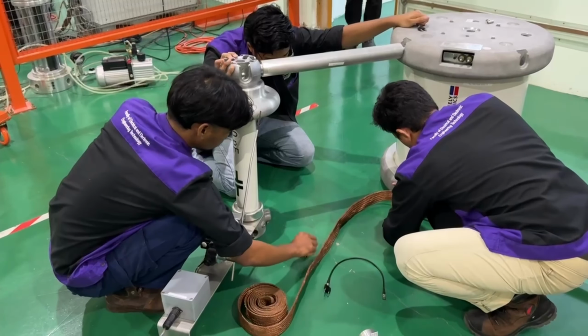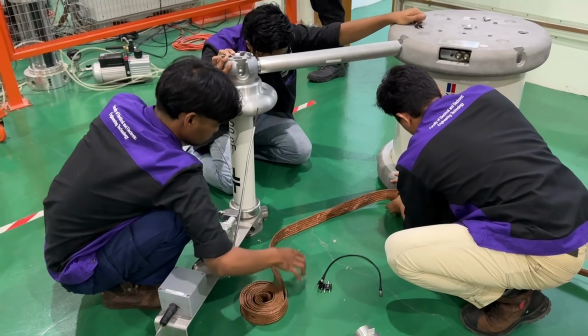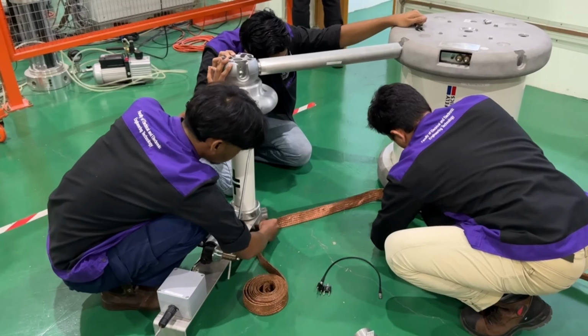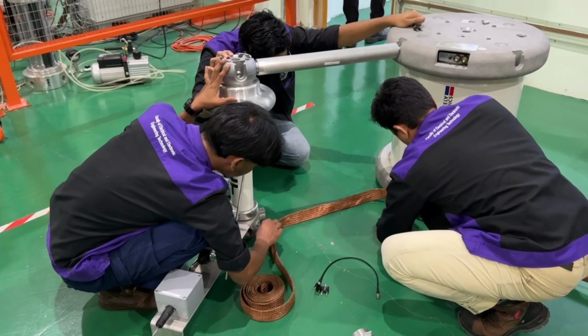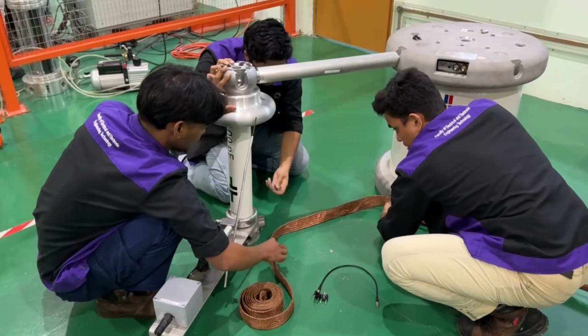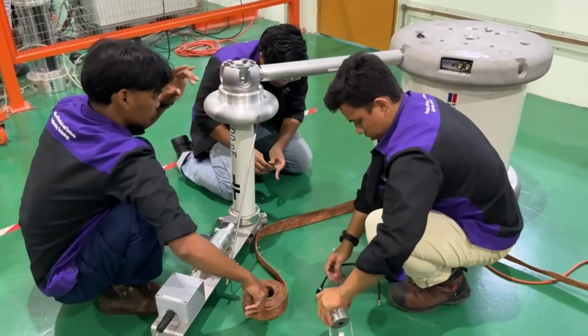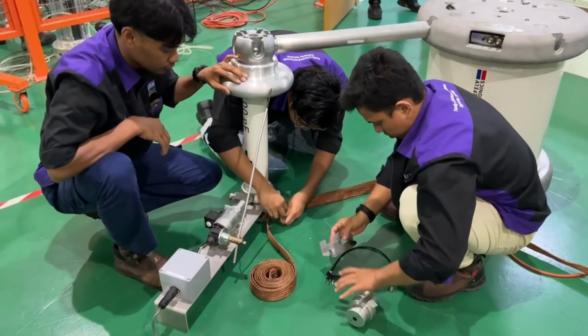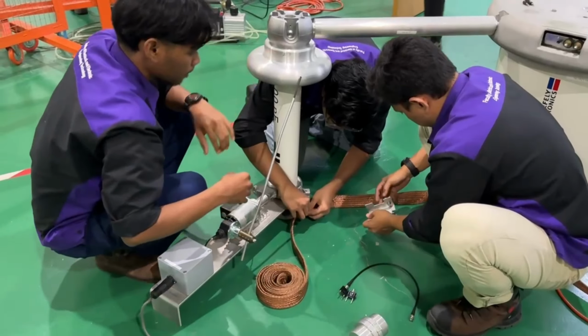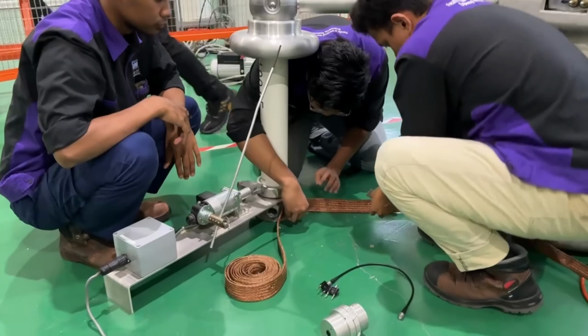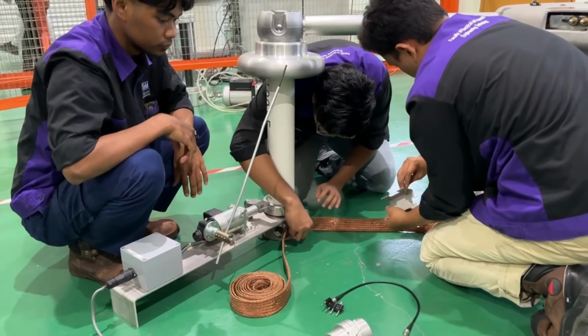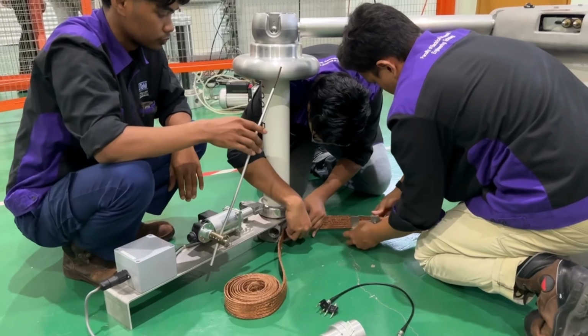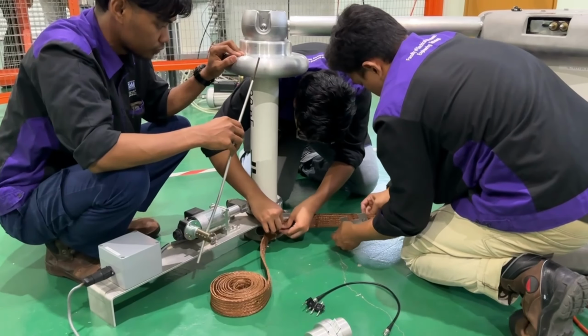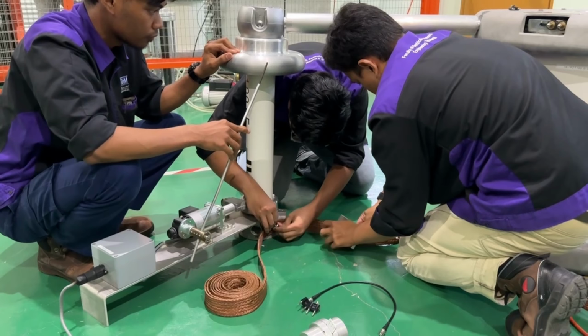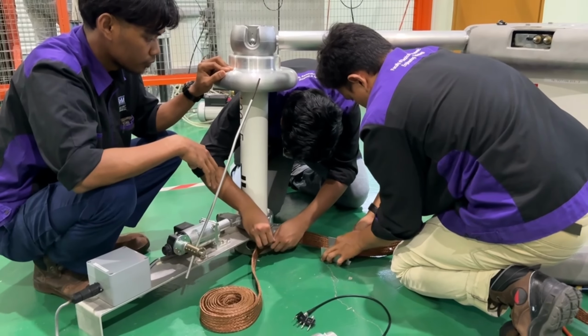So we proceed to the grounding process. Prepare the copper braided and ensure the copper braided has a pre-drilled hole for easy attachment. Unscrew the nut from the transformer grounding terminal and insert the hole of the copper braided into the terminal. Secure it properly and tighten the nut. Make another hole in the same copper braided for the next connection and unscrew the nut from the floor pedestal grounding point. Place the second hole of the copper braided into the pedestal terminal and screw it tightly.